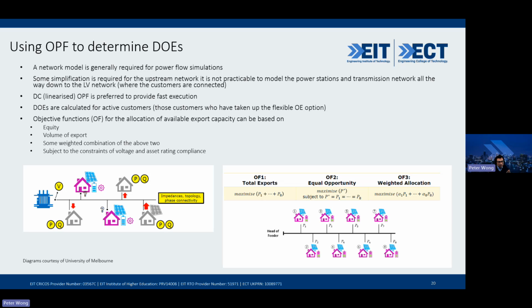The issue with equity is that generally the customers closest to the distribution substation are going to be the ones, by the law of physics, who are able to export more compared with the one at the end of the LV feeder. So if you go by the equity principle, the customer at the end of the LV feeder is the one that determines what everybody gets to export. So if the limit at the end of the LV feeder is only 2 kilowatts, then every active customer on that LV feeder is going to get 2 kilowatts. Now, obviously, you can see this is not going to be the best way of maximizing the solar generation.